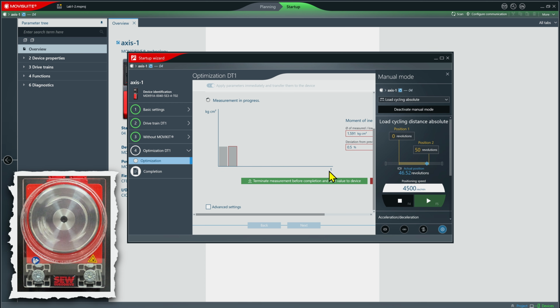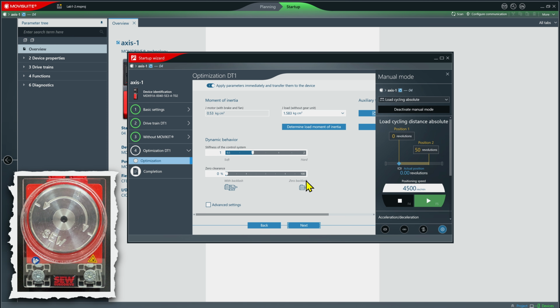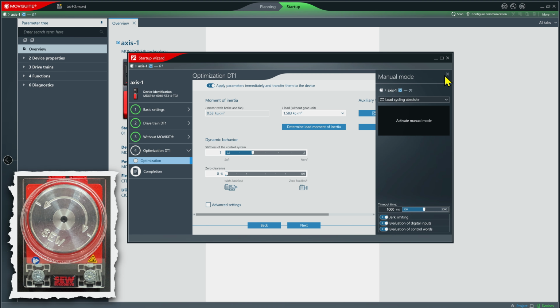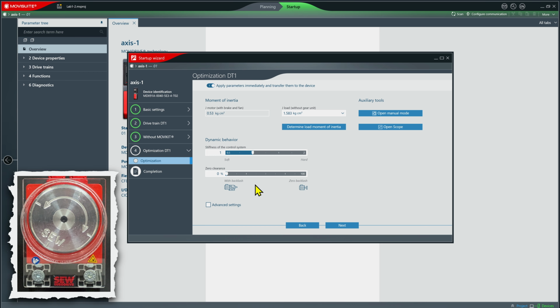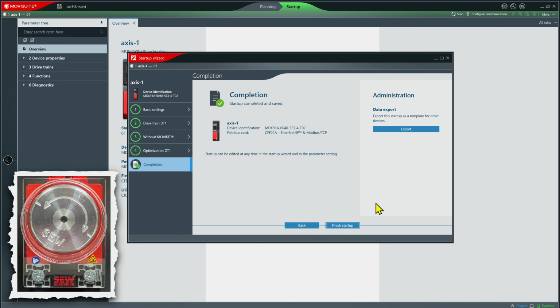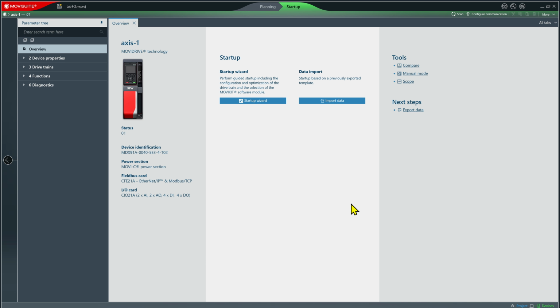Our bar graph appears. The bars are all about the same height and the button is turned green, so I can click End it and accept the value. I can stop my motor from cycling, deactivate manual mode, and I'm going to remove controller inhibit here and go ahead and do that. Close it up. I do need to set my backlash slider to 100% because we have no gearbox. And that's it. Click Next, and it says, hey, you're done. All right, finish startup. And that is that.